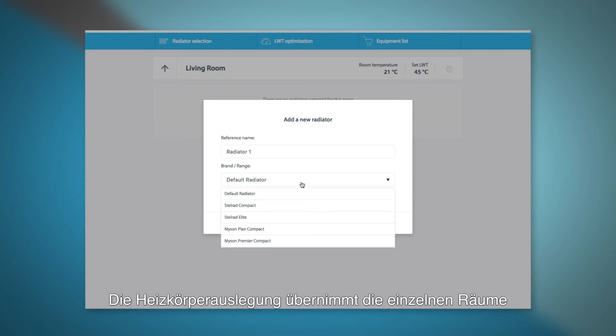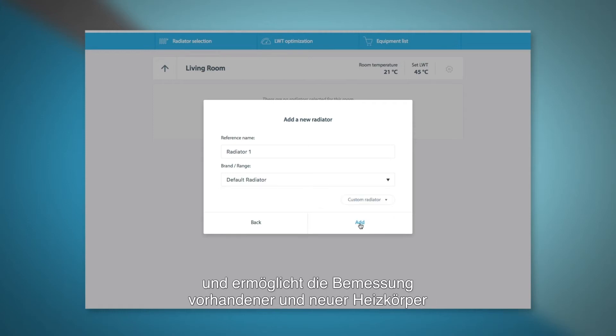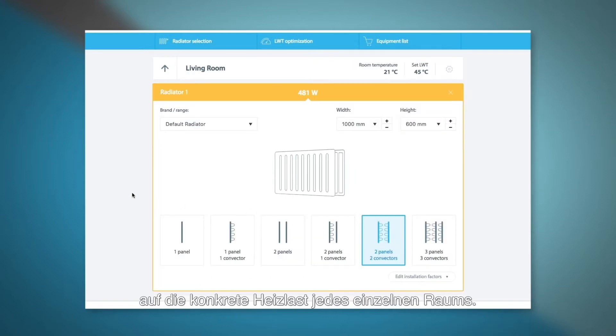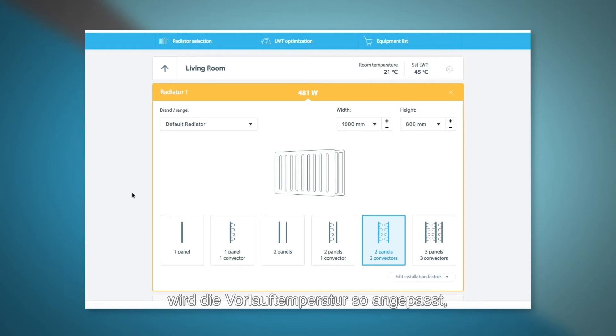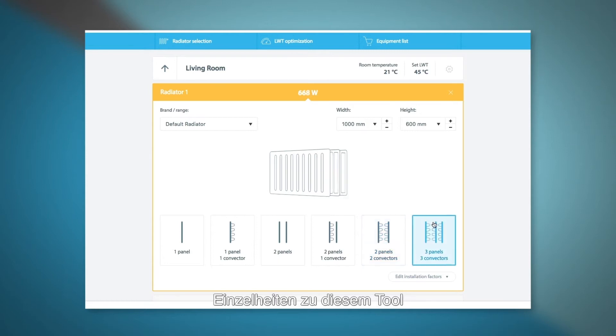The radiator selector takes the individual rooms from the room by room heat load calculator and allows you to size existing and new radiators in each room to ensure the heat load for that specific room is met. Depending on whether the radiators are sufficiently sized or not, the system flow temperature adjusts to ensure the room temperature is reached. For further information on this tool, please watch our additional video.